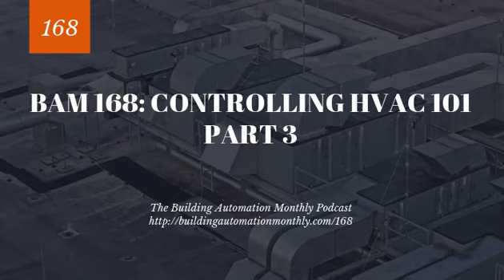On air-cooled chillers, it's basically the same thing, minus the cooling tower. You now have some fans that are pulling air through this condenser coil, or you're just using natural airflow. This is why it's bad to put air-cooled chillers in a corner surrounded by 8-foot fences next to a building, because you want to keep them quiet, but now they're not getting any airflow and they can't really transfer heat as well as they should. So yeah, if you've ever wondered about why that's bad.